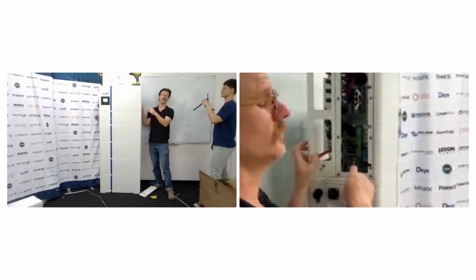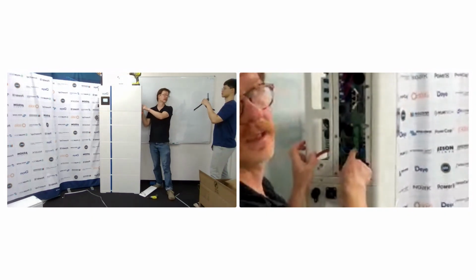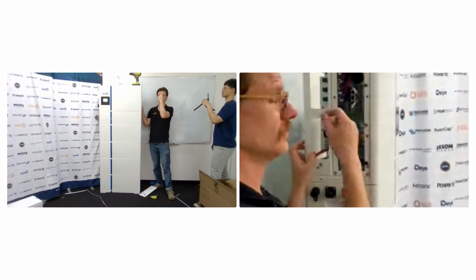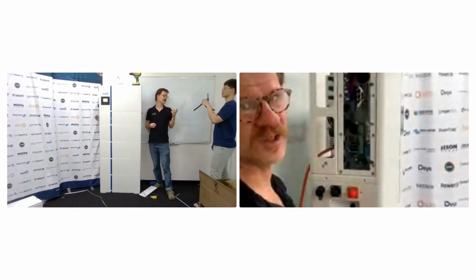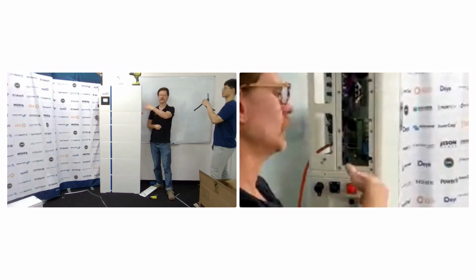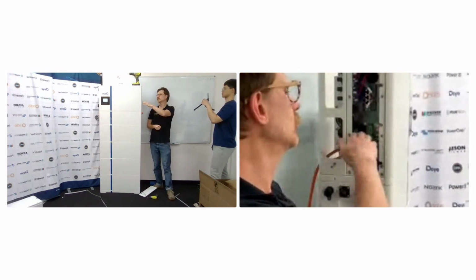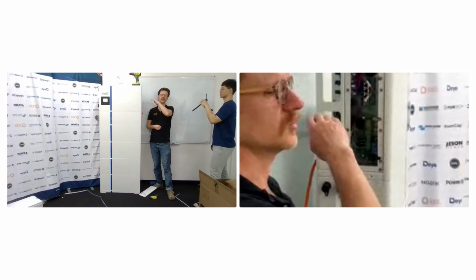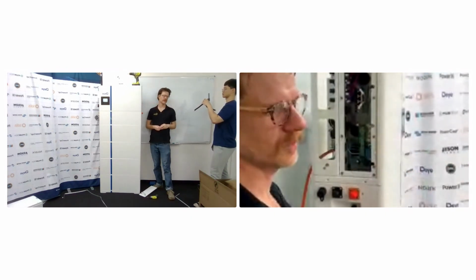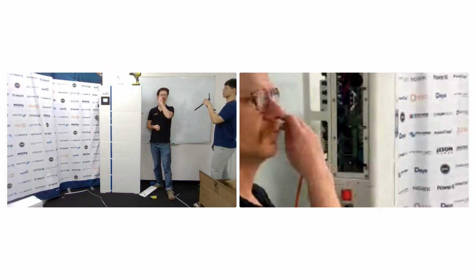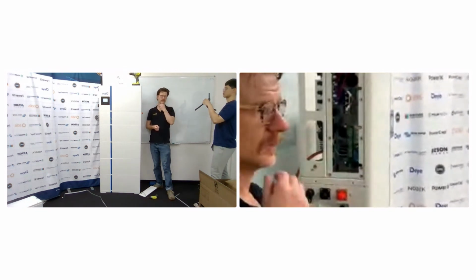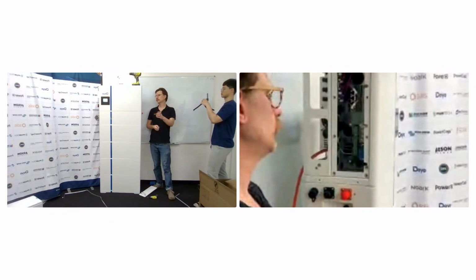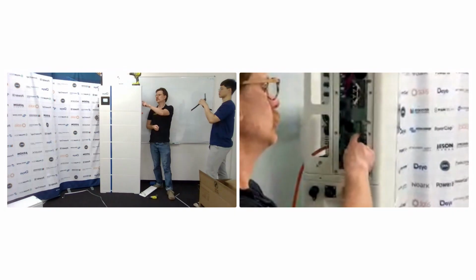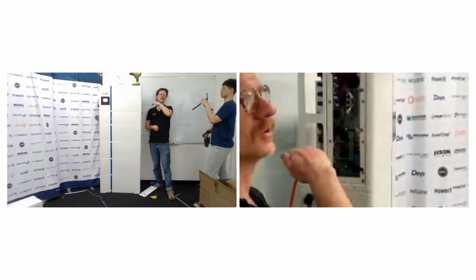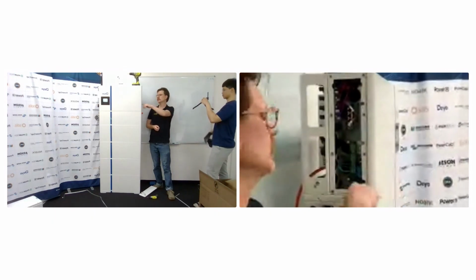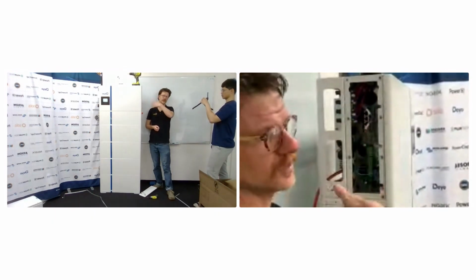You can actually just put, if you're off grid, the generator into here instead, and then you can use that as what they call a smart load port, because it's just a contactor on the AC bus. So instead of it controlling the generator input, it can just be a smart load output. So you just turn it off when the battery's at a certain state of charge, or you can use it for an AC coupled inverter. Maybe you've got an existing one, and instead of putting the AC coupled inverter on the load output, you could put it on the gen port, and then it would be able to turn off the AC coupled inverter without turning the loads off if it wanted to. But it will frequency shift the AC coupled inverter.